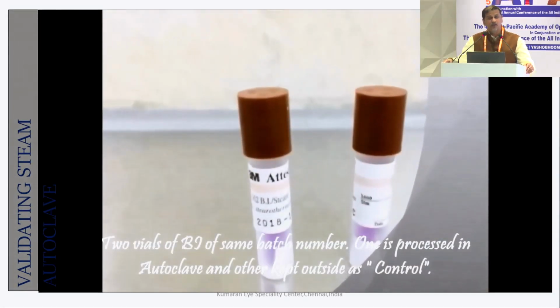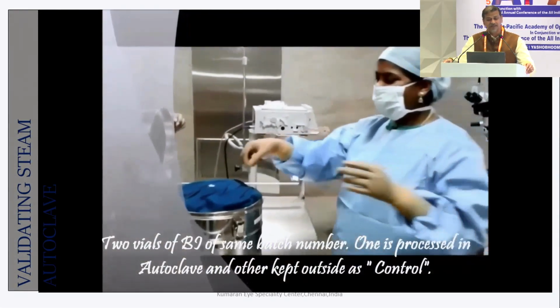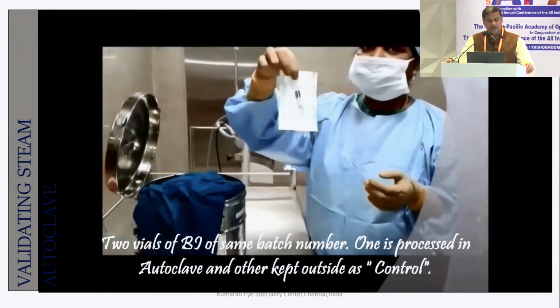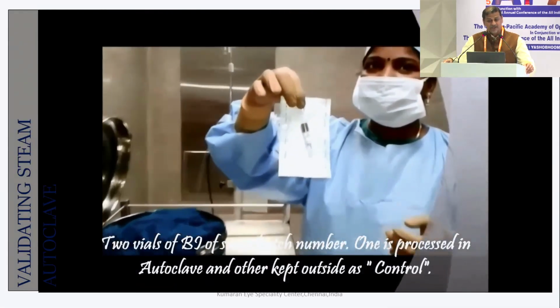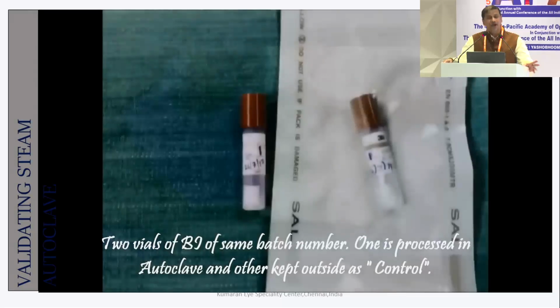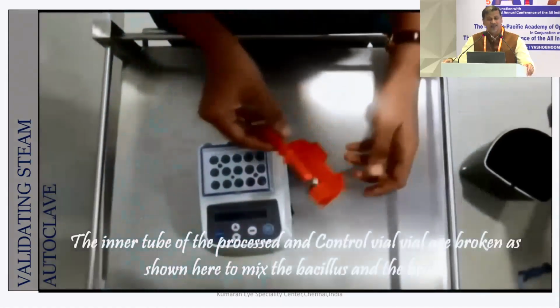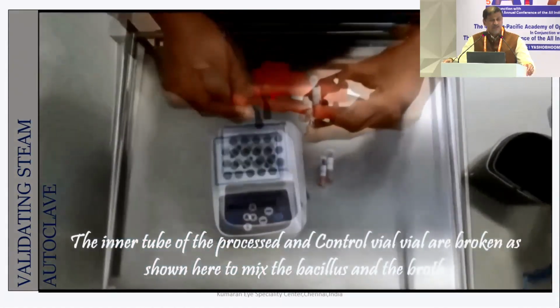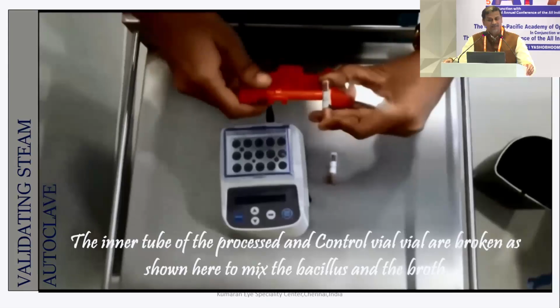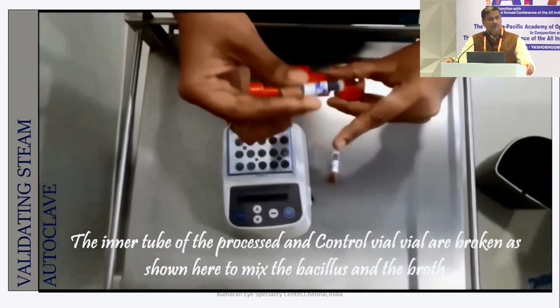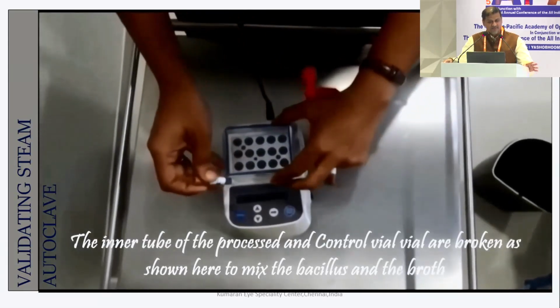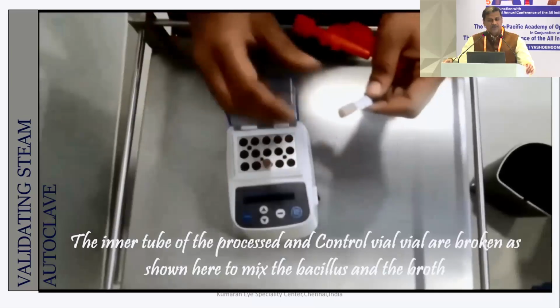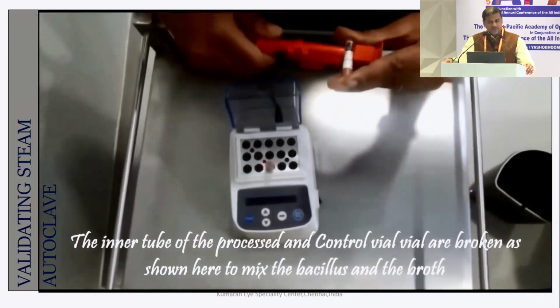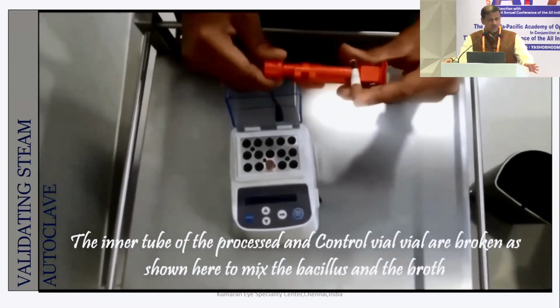The biological indicator is very important. As I told you earlier, one is kept outside and the other is processed inside the sterilizer. Once this is coming out, to understand the biological indicator, it consists of two tubes. The outer one is a silicone tube and the inner one is a glass tube which has a broth inside. So break the glass tube so that the indicator and the broth are mixed, and this is incubated in a biological indicator incubator which is easily available and not very expensive.